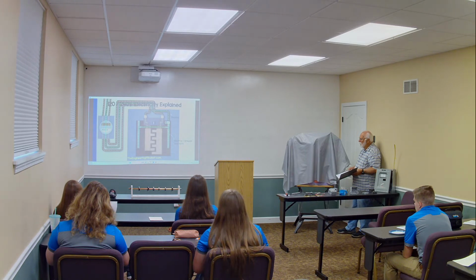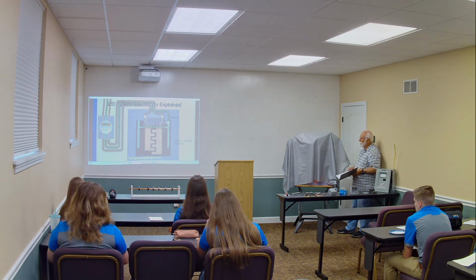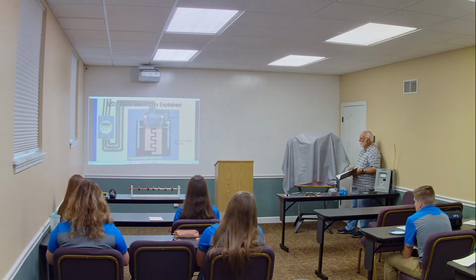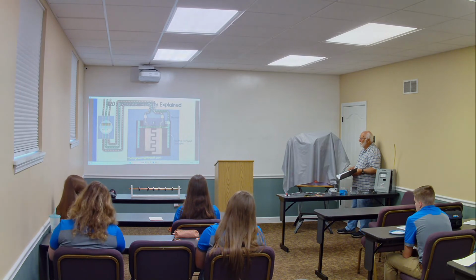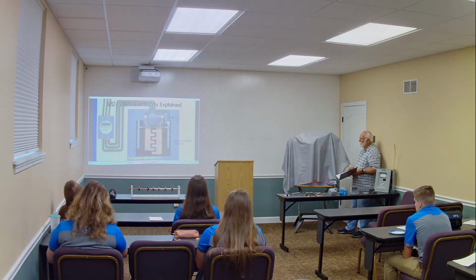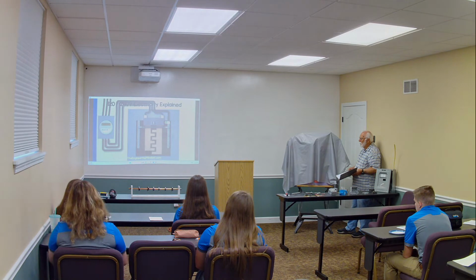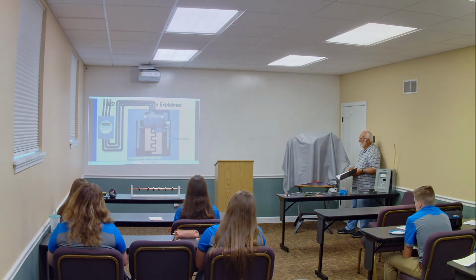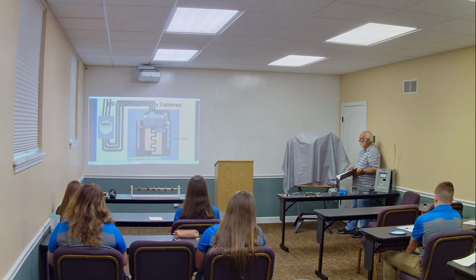So the two hot wires will provide electricity, and once it is used, it will return to the transformer via the neutral bar. It is still AC alternating current, but to make it easier to visualize, I've only animated the current flowing in one direction, so you can see the path. Now coming back to the panel, connected to the bus bar, we'll have our circuit breakers. These will look something like this with this black plastic casing and a toggle switch on top. The circuit breaker controls the flow of electricity into individual circuits in the property.